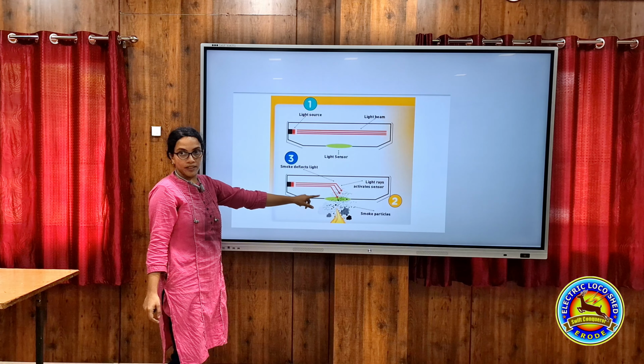As I said, the smoke is collected from all parts of the locomotive and sent to the FDU. And there is airflow monitoring, so if the pipeline is broken or blocked, the airflow will be monitored and a fault is transferred to the VCU.